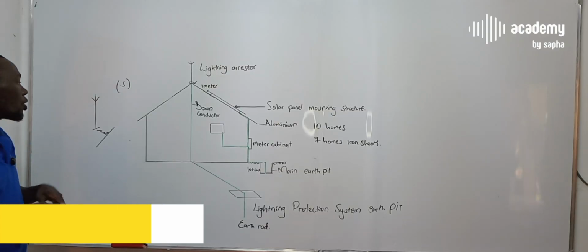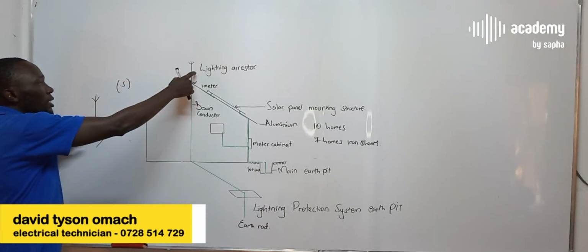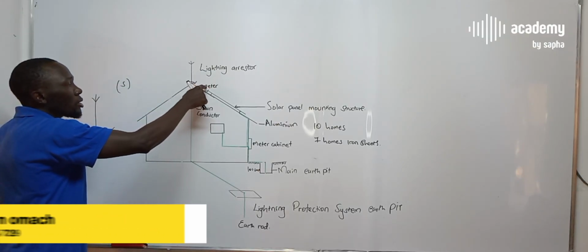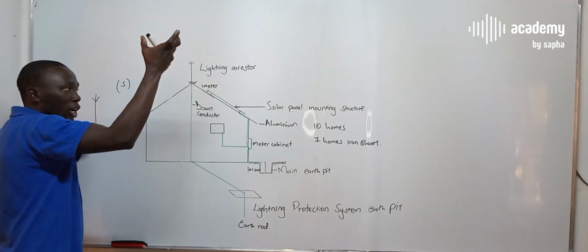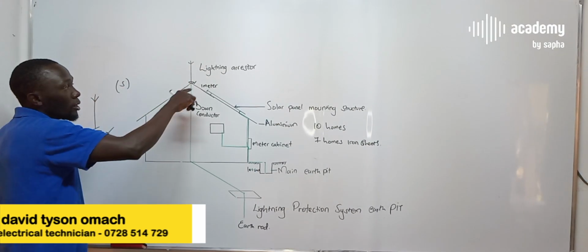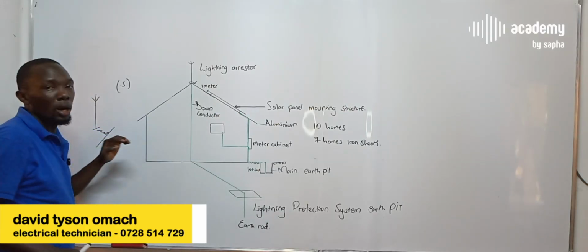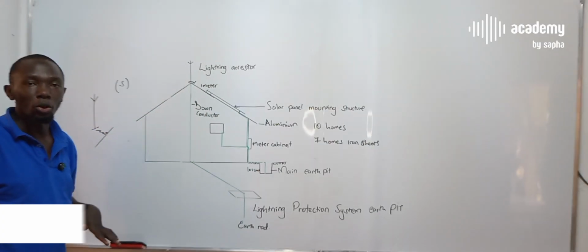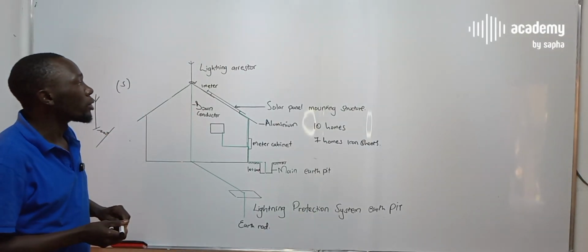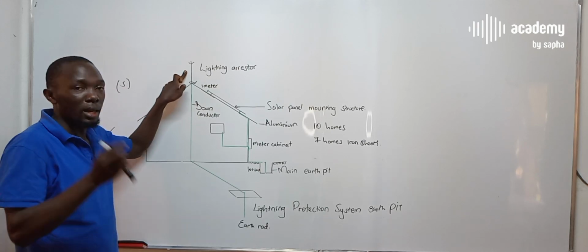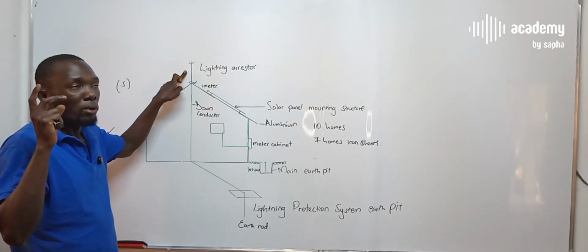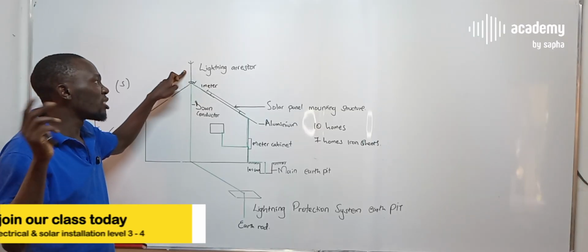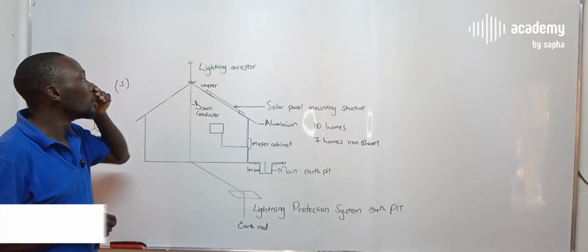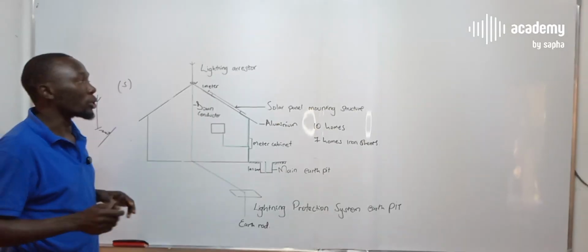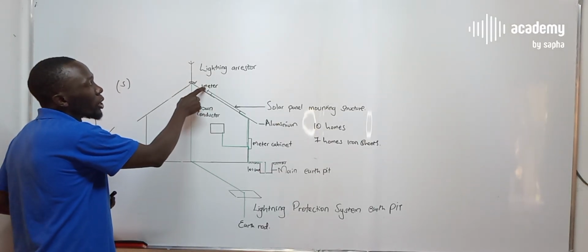So when we have two metals close to each other, the lightning arrestor and another metal, if it's less than 1 meter and there is enough charge from a proper lightning strike, it will flash and hit either your panels or any other electrical component. So that is number one: there has to be a proper distance between the lightning arrestor antenna - or we can call it an antenna or a rod, different regulations call it differently - and any metallic part should be 1 meter or even more.